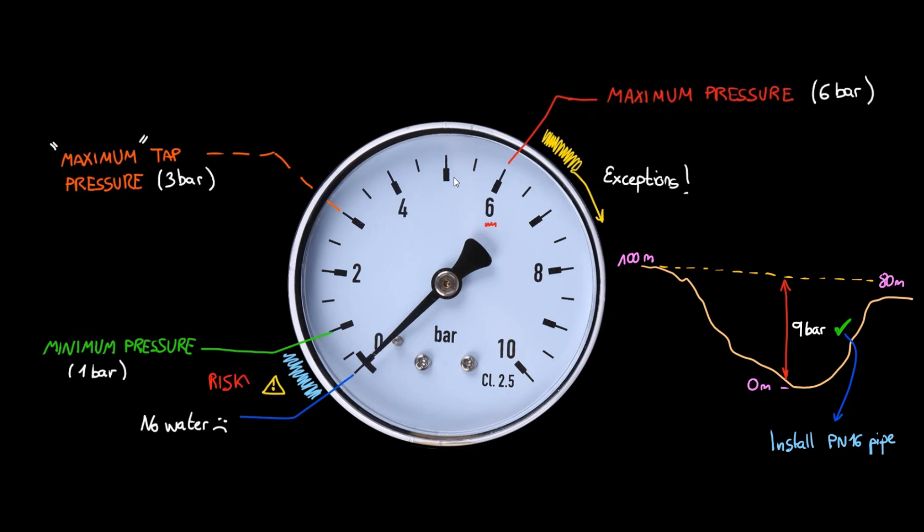Pressures below 10 meters are risky for many reasons. Technically, it is risky because there's little room for surveying errors and other unpredicted situations. The pipes carrying capacity declines over time, and trapped air can completely block pipes with little pressure.